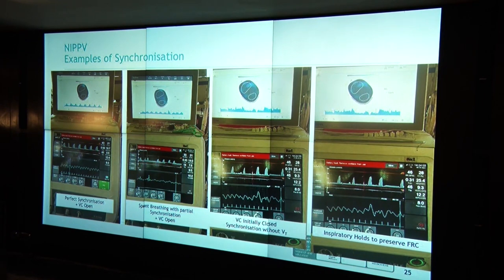It's measuring what's actually happening in the lung. So if you've got a closed vocal cord, or pressure being delivered by the ventilator that isn't being transmitted, we can see that - as opposed to measuring it off the ventilator, where the flow sensor will just say you gave the volume, therefore it must have gone in.